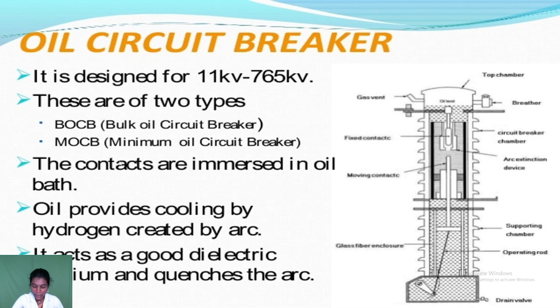Then the contacts are immersed in an oil bath. The oil provides cooling by the hydrogen created by the arc, because we want to control the arc. Only then are we using oil as the medium. Mineral oil has better insulating property than air. The oil is used to insulate between the phases and between the phases and the ground, and for the extinction of the arc. So it acts as a good dielectric medium and helps quench the arc.